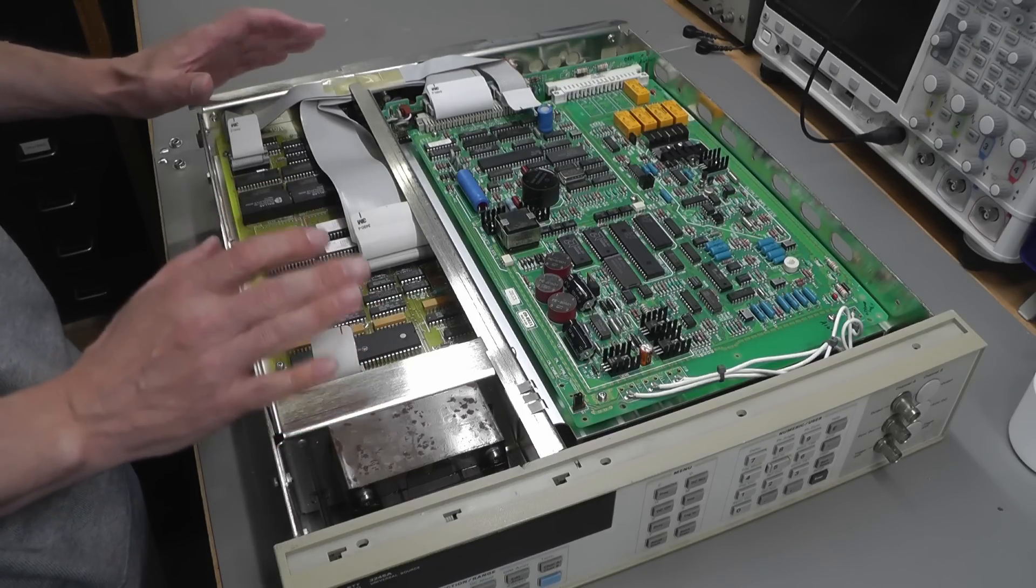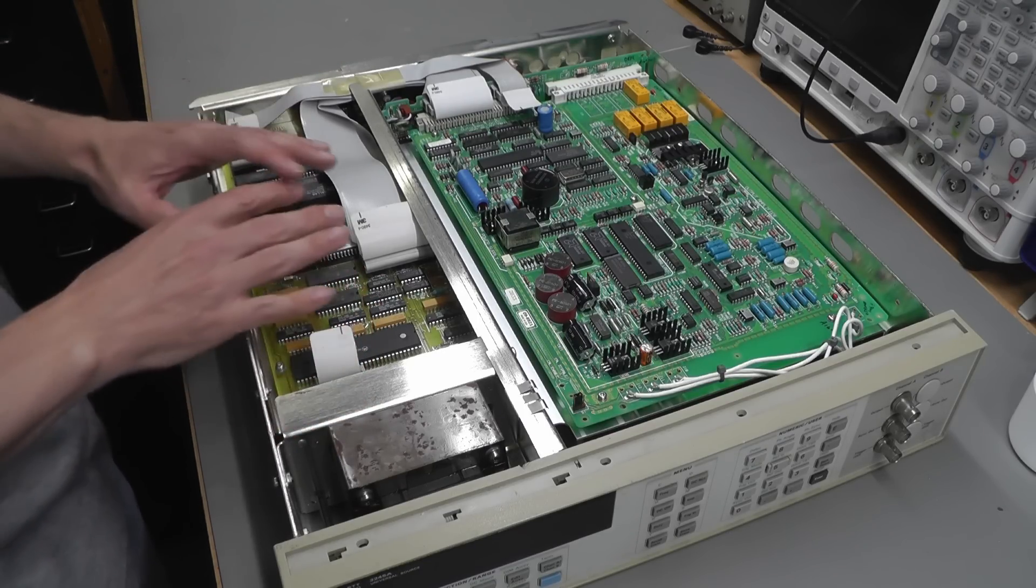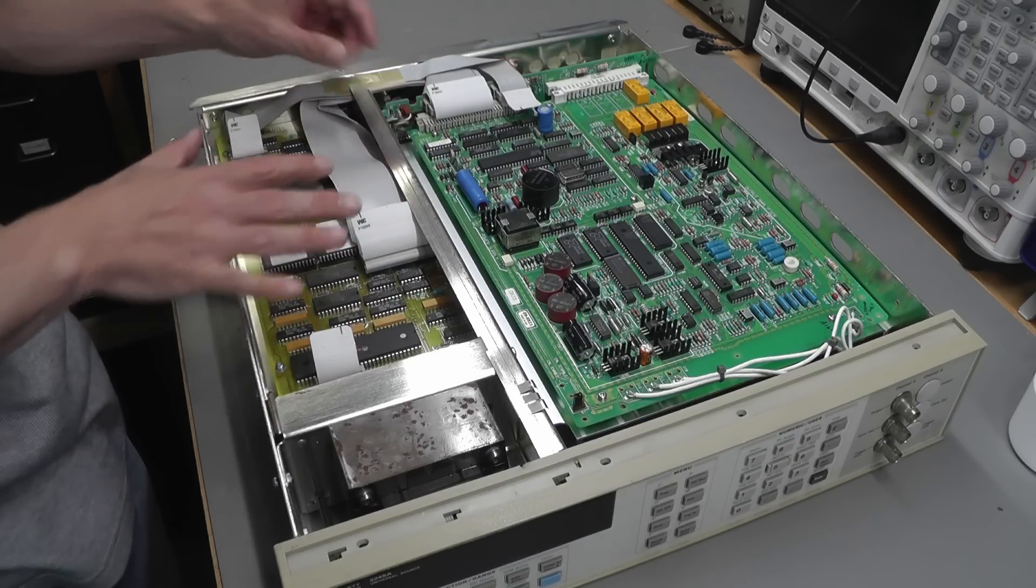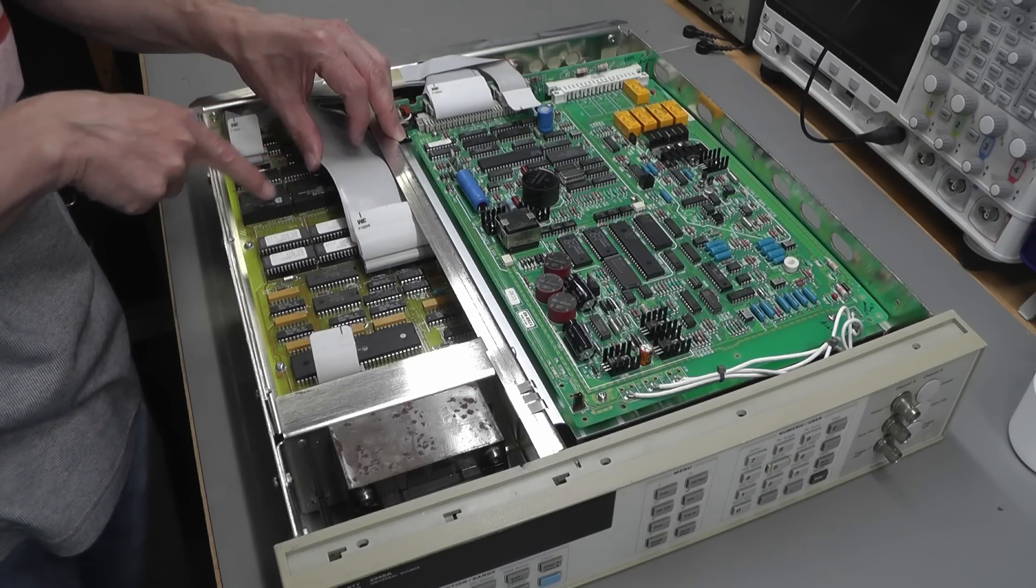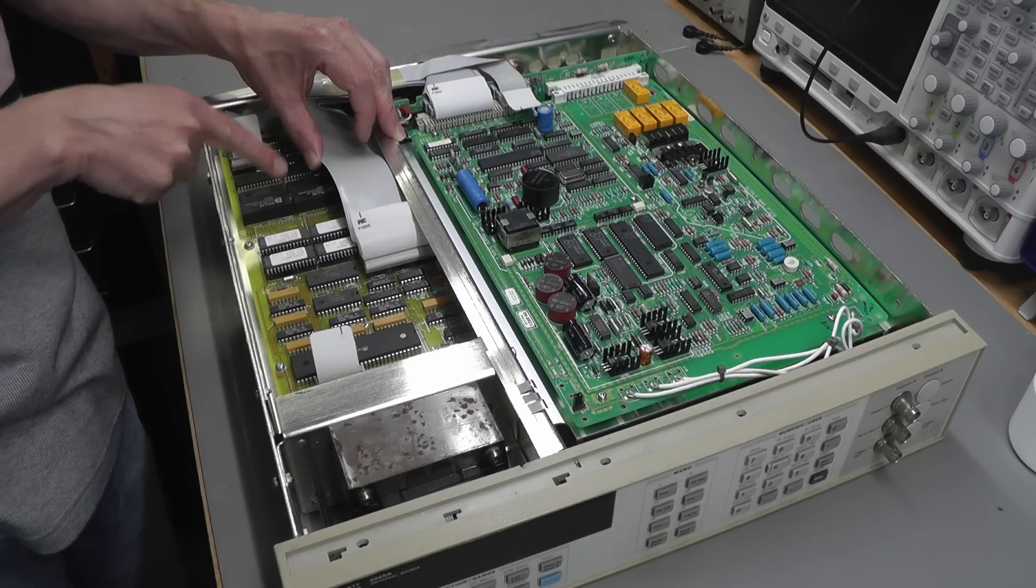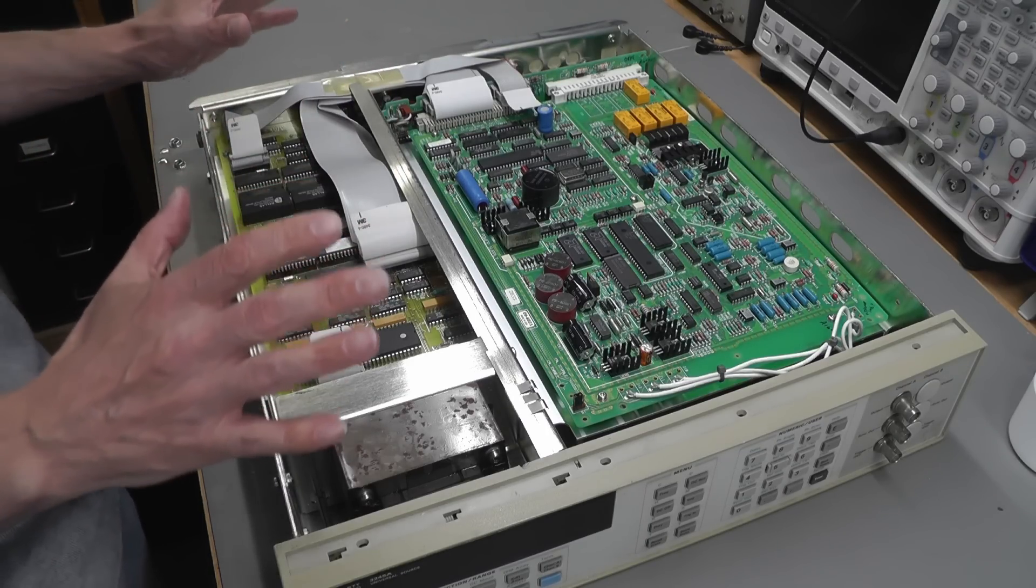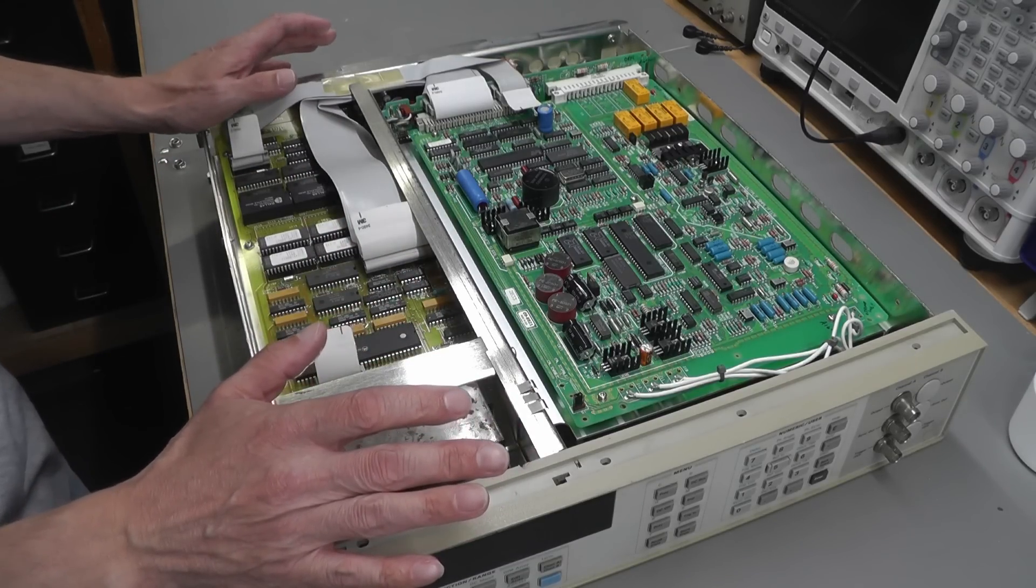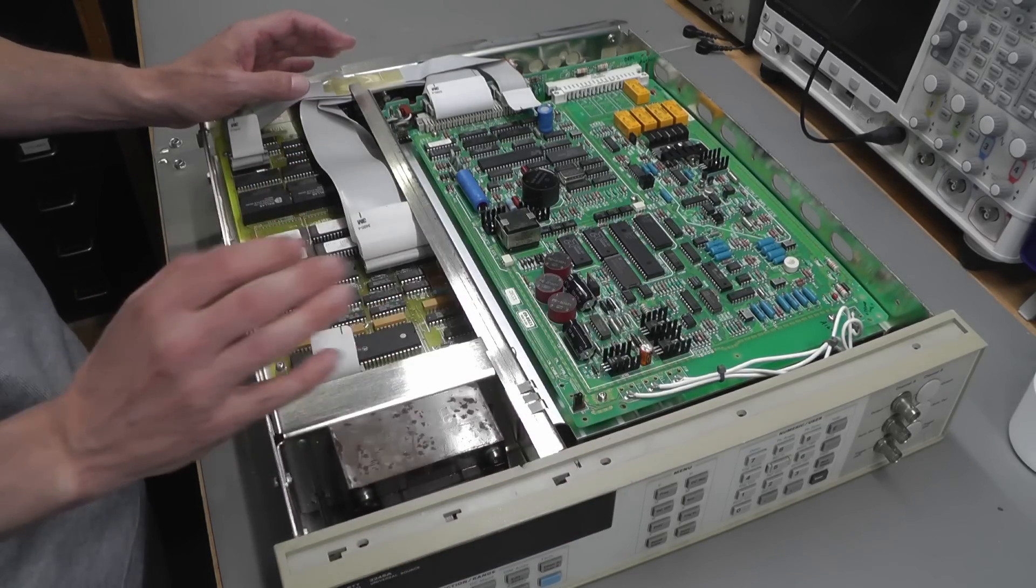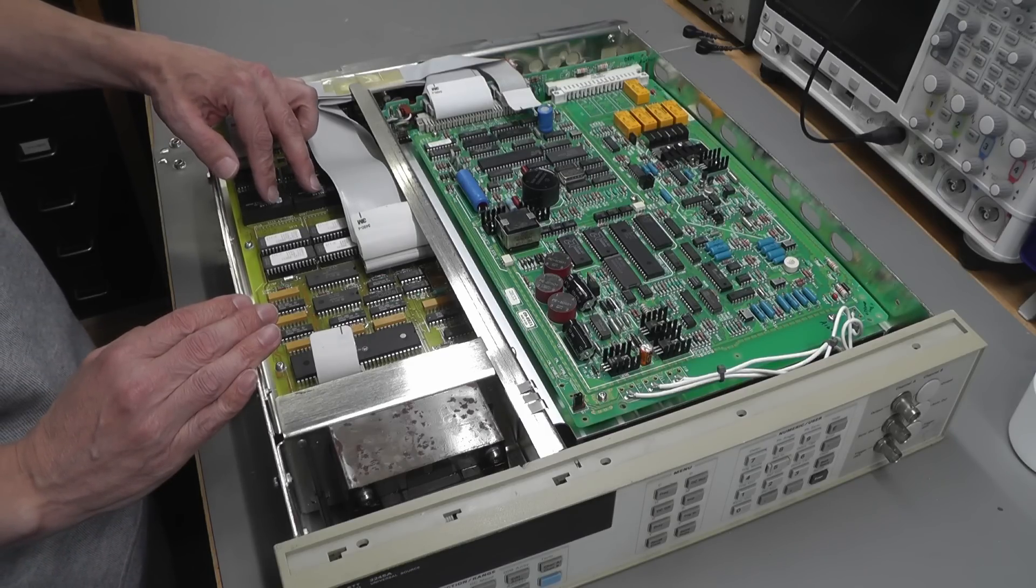Here we have the A5 board, the out guard controller. This is the main processor board—you can see the EPROMs on the board. And crucially there's those two Dallas battery-backed RAMs, DS1235. I will be changing them out. I'm actually going to do that right now before I tear this thing apart. I'd like to see if we could clear those errors, both of those errors in fact, just by replacing these two Dallas RAMs.